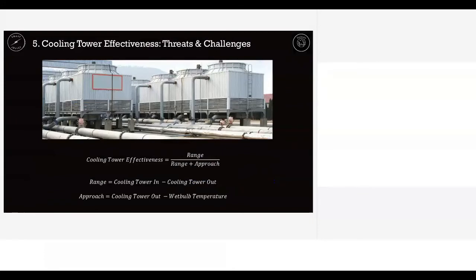So again, some basics about the cooling tower. The lower the approach, the better it is. But if you want to make a low approach cooling tower, your initial cost would be very high. The approach is the difference between the wet bulb temperature and the cooling tower outlet temperature. This is cooling tower in and this is cooling tower out. The outside temperature is the wet bulb temperature, and this cooling tower is trying to dissipate heat to the outside. I'm not going into the theory of this heat exchanger, but still.